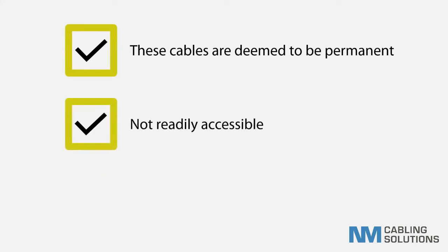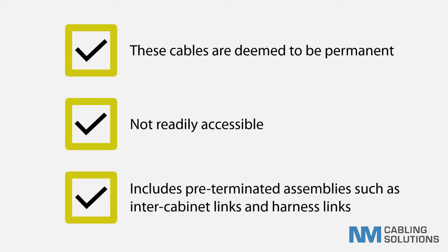The first covers installation cables and the actual clause is shown here. For further clarity, these cables are deemed to be permanent and not readily accessible. By the wording, this also includes inter and intra cabinet links such as switch links, even though some may mistakenly view these as long patch leads. If they are routed within the cabinets and along pathways in such a way so they are not easily removed, then they are in scope of the CPR and need to be made from compliant cable.